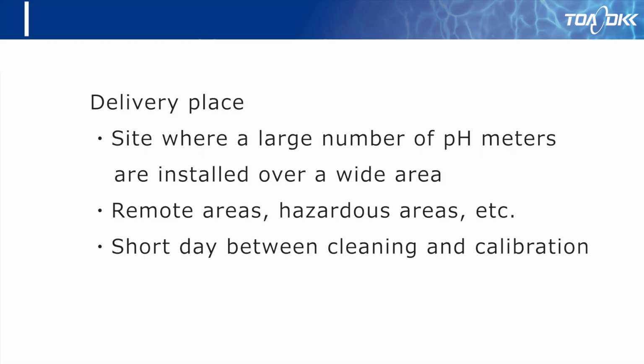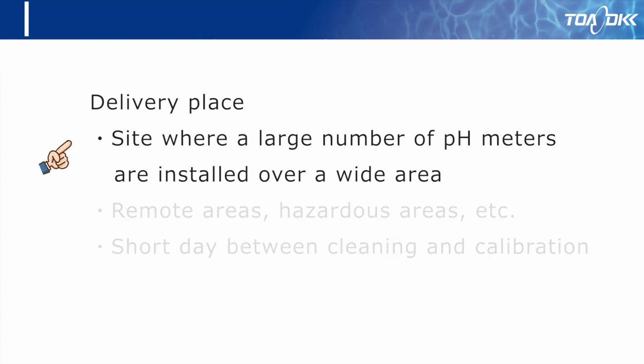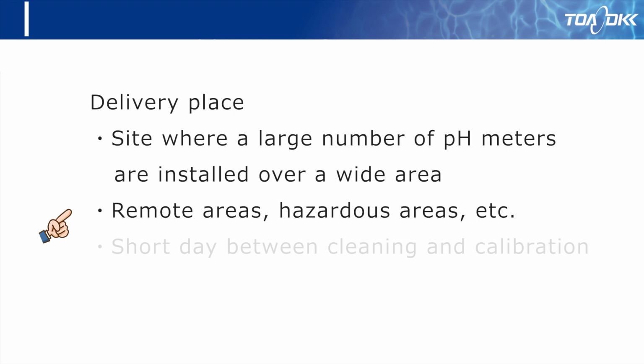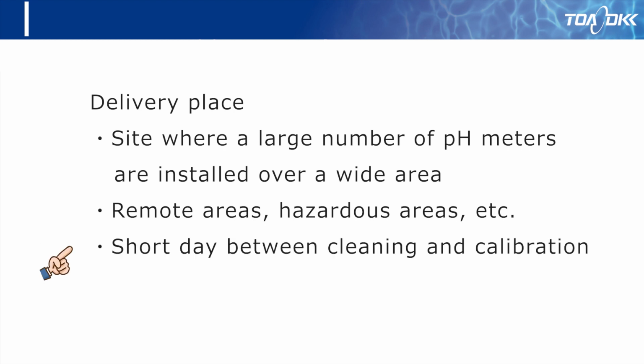It is mainly used for locations where a large number of pH meters are installed covering a wide range, remote locations, and hazardous locations where frequent calibration is difficult to be performed. Especially, a location where the interval of cleaning and calibrating is short is recommended to be installed.